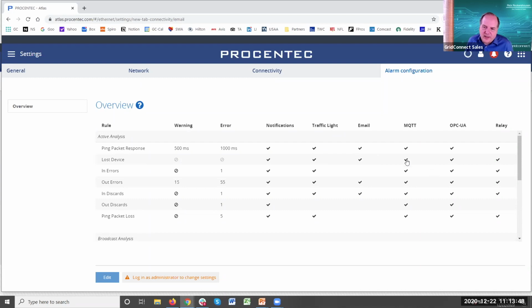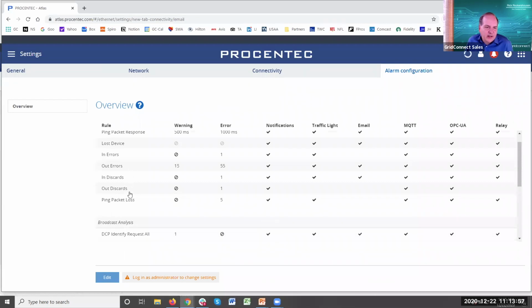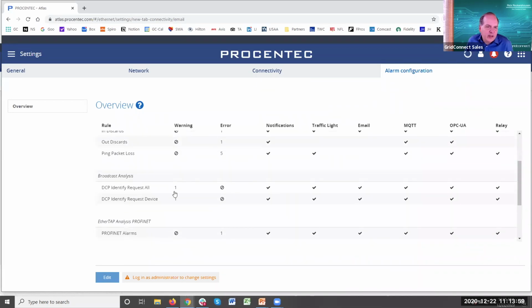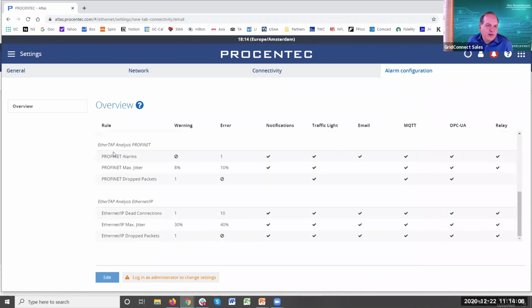You can also send it, as I mentioned earlier, out MQTT, OPC-UA, or turn on the relay. These are the different kinds of errors. If you scroll down here, here's some Profinet related things that you might want to alarm on. And then when you use your Ethertap analysis for Profinet, these are the alarms, and you can change these thresholds, what would be acceptable jitter for you and your network. Here's the same things for Ethernet IP, and there will be new stuff here for EtherCAT very soon.